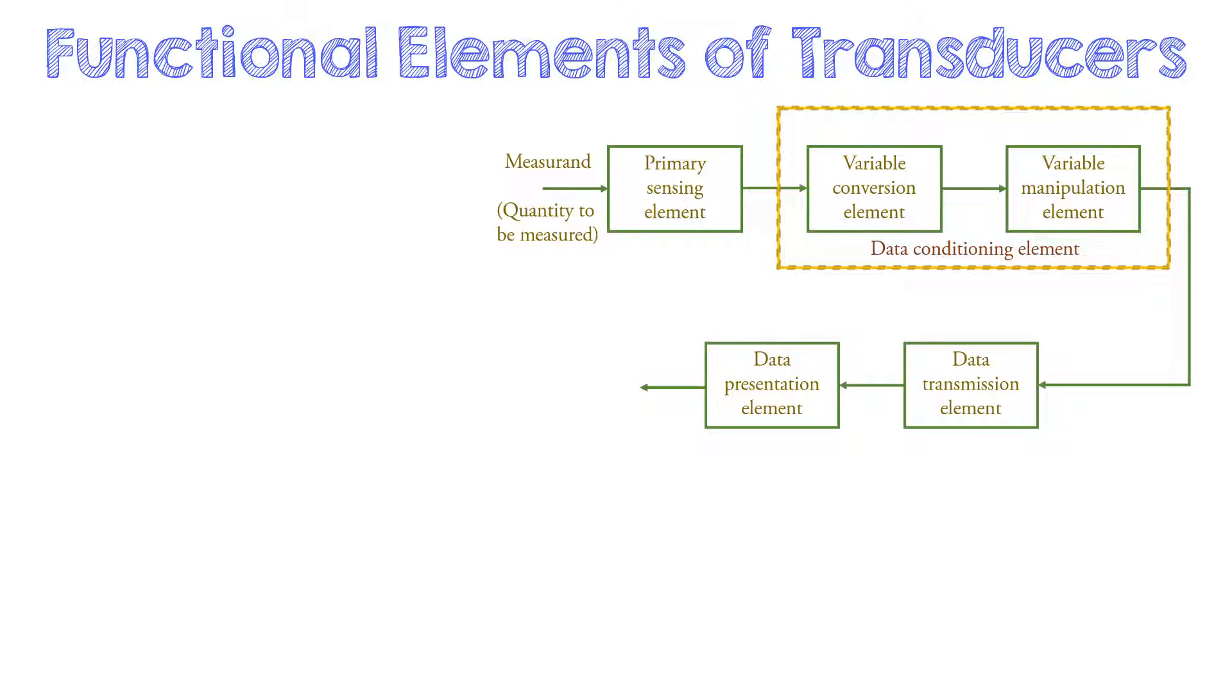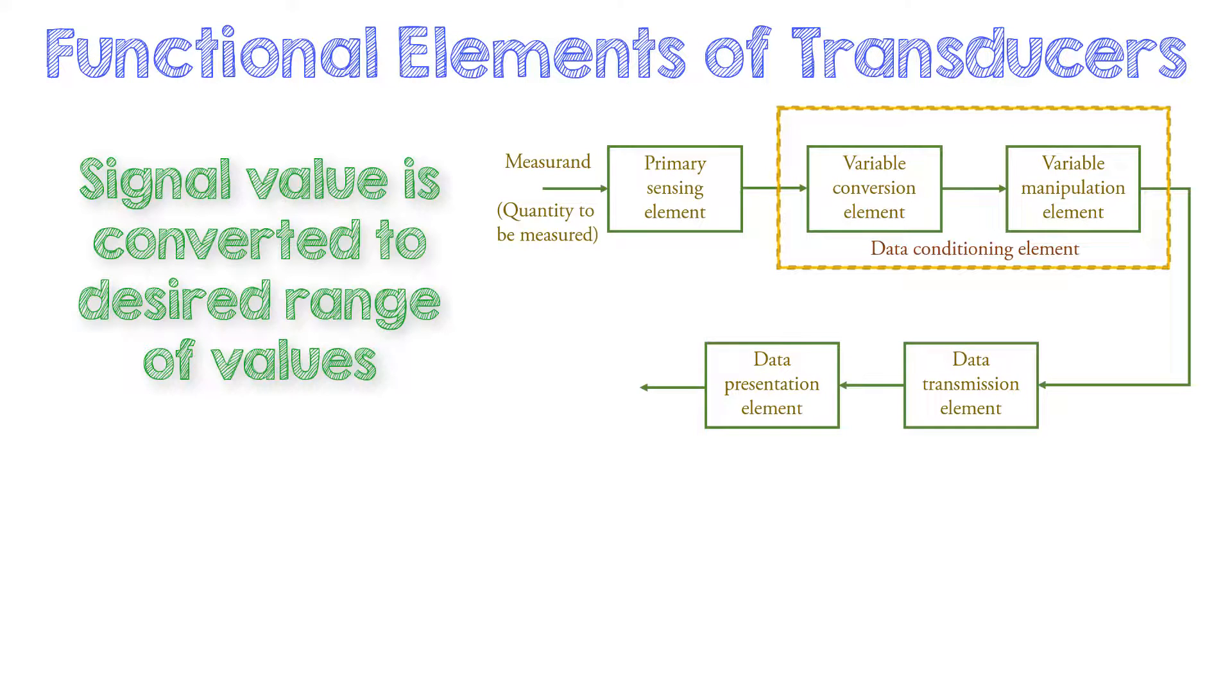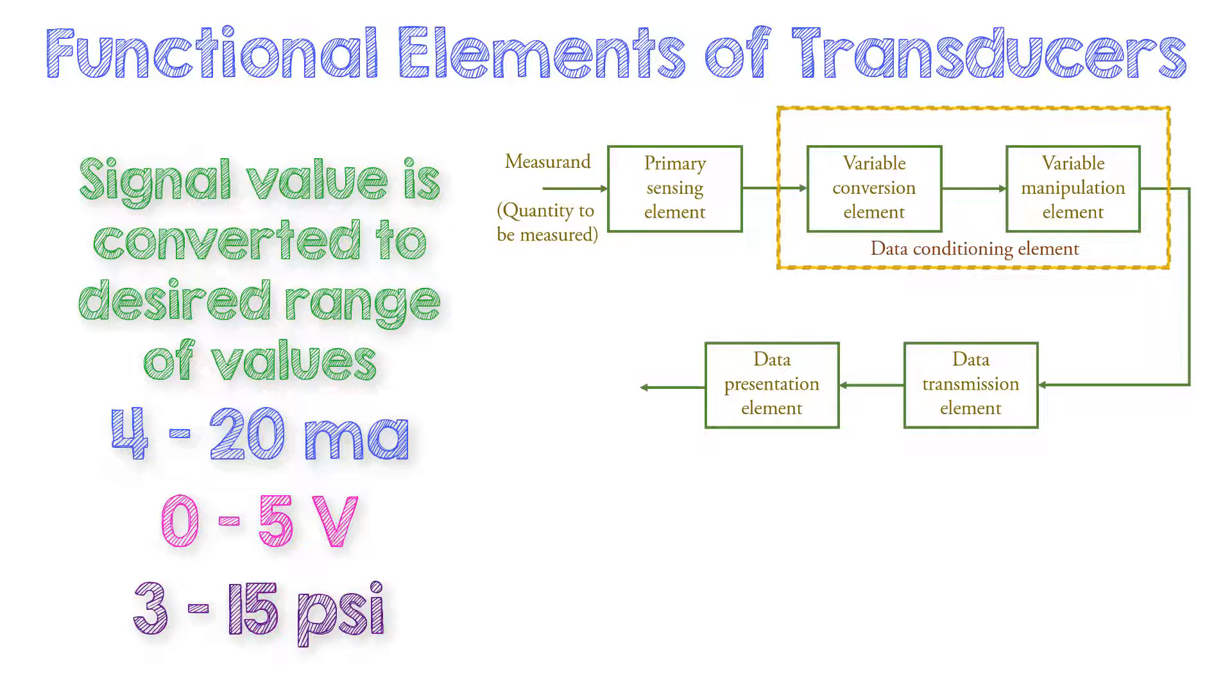The next block is variable manipulation element. Here, the signal value is changed to get a desired range of values. Generally, the accepted signal ranges in any process industries are 4 to 20 mA, 0 to 5 V, or 3 to 15 PSI. Variable manipulation element can help achieve these standard ranges using signal conditioning circuits.